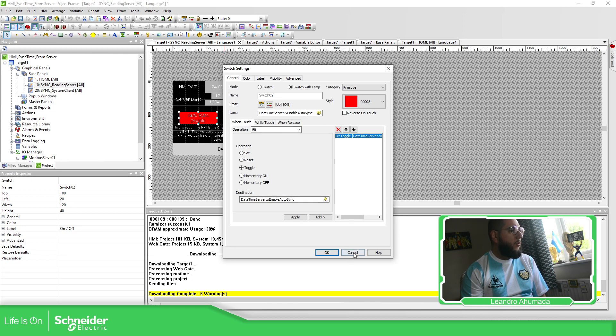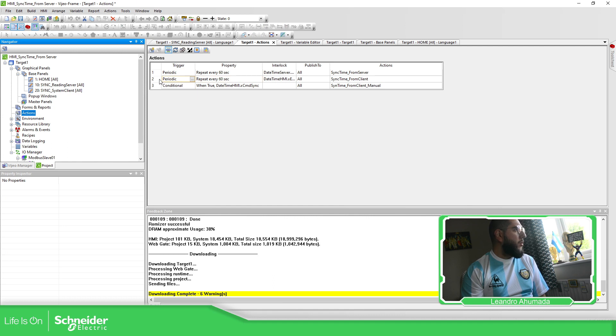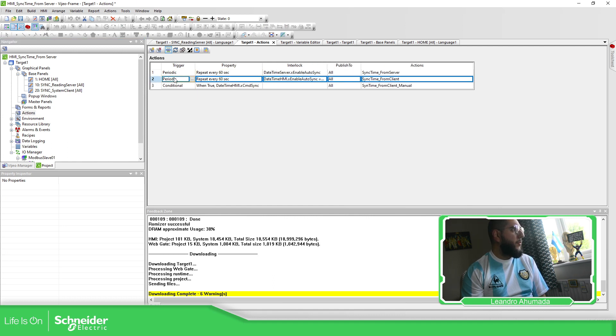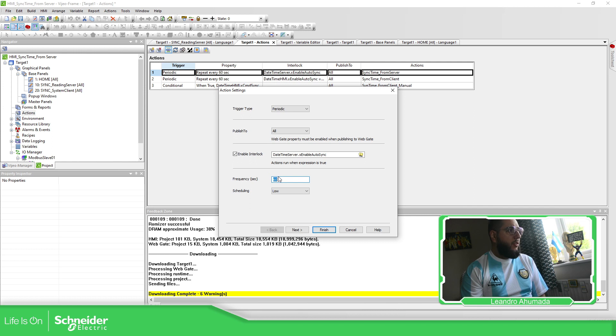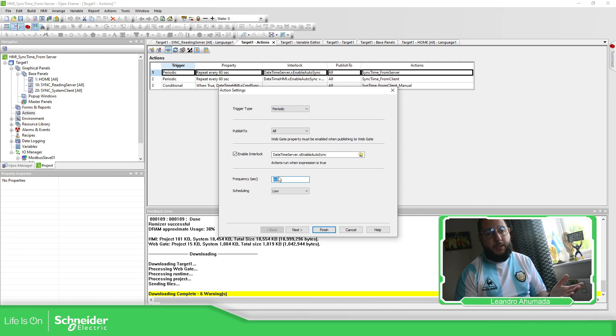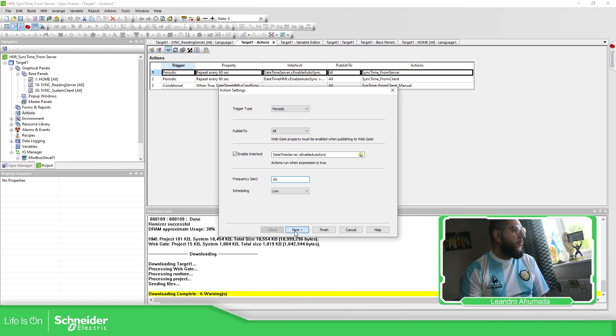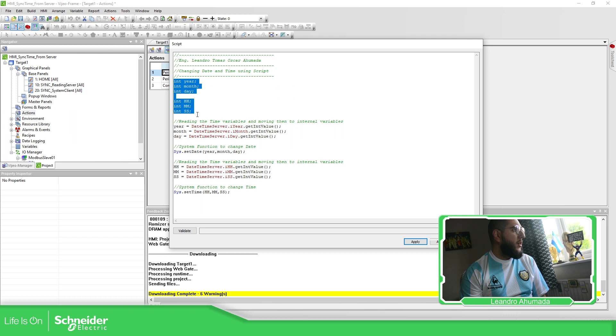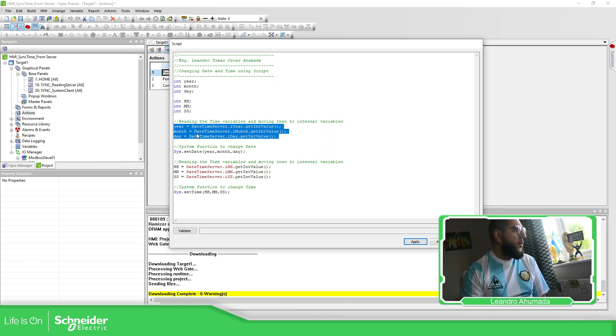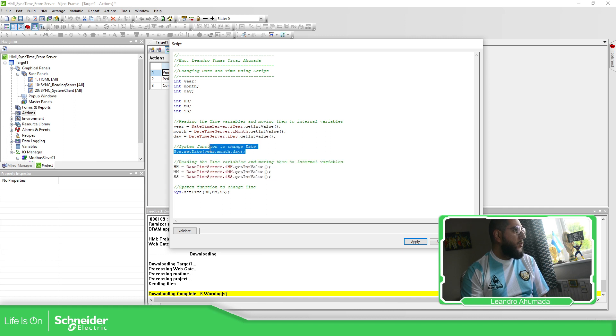In order to update the date and time, I've used a bit to automatically trigger it. What it does is run a script. For the server, I've defined a periodic trigger every 60 seconds — you can change this to five minutes or a lower interval. The script creates some internal variables for date and time, reads from the server the date and time variables, and then uses the functions sys.setDate and sys.setTime to change the date and time on the HMI.